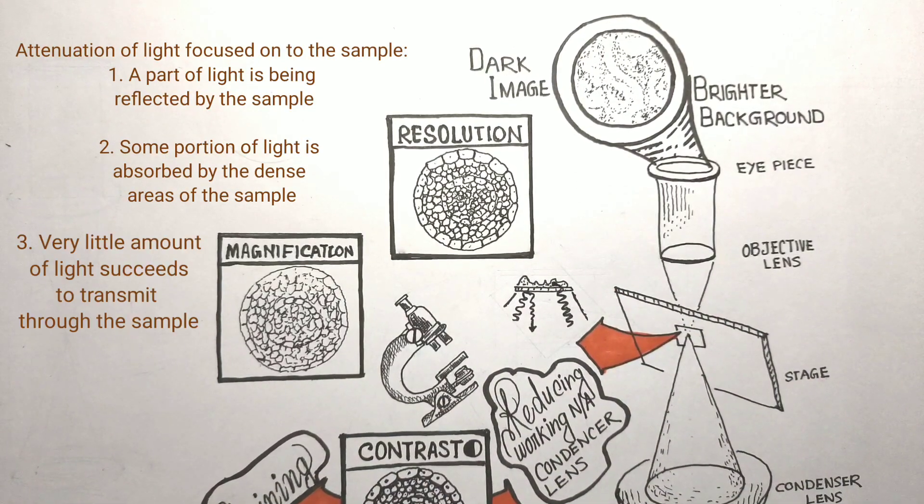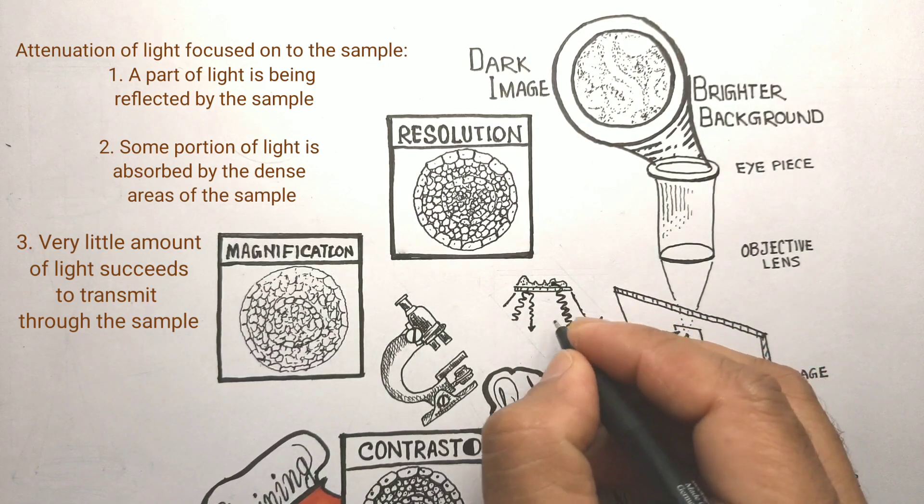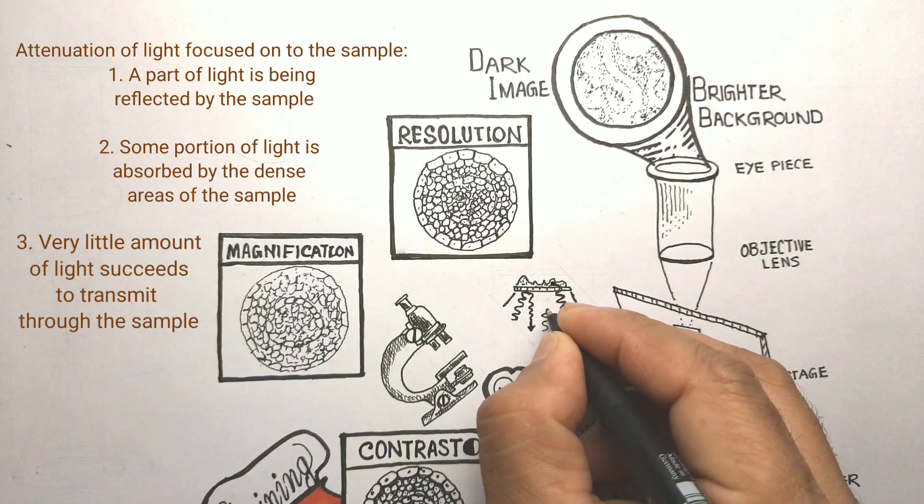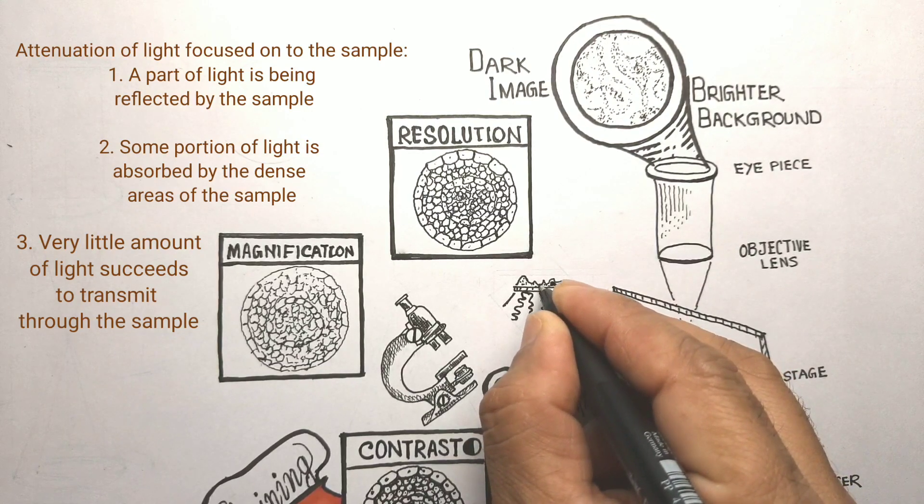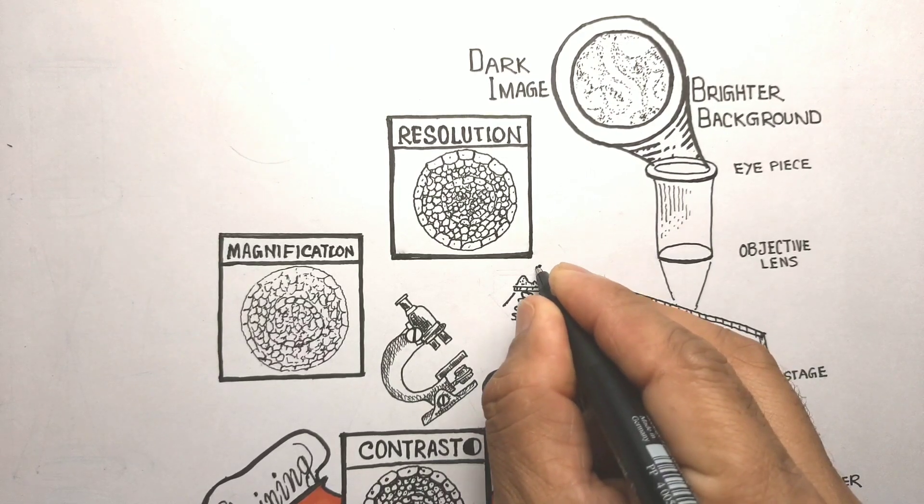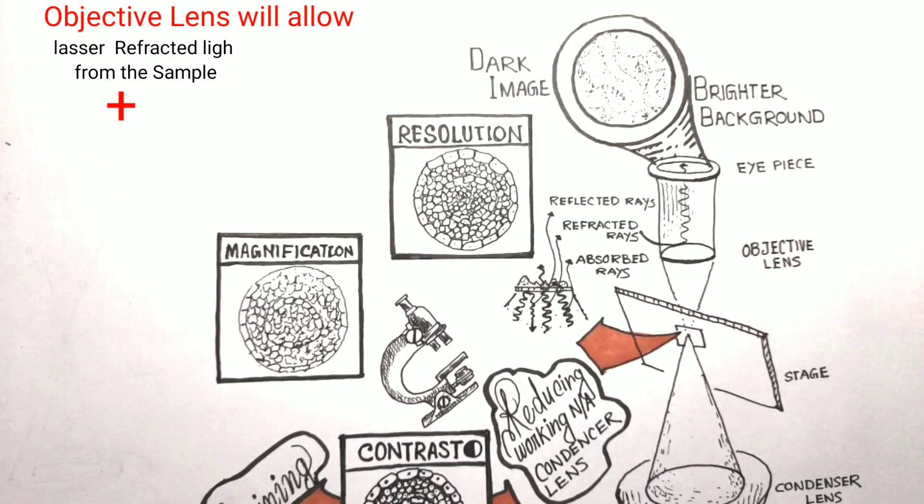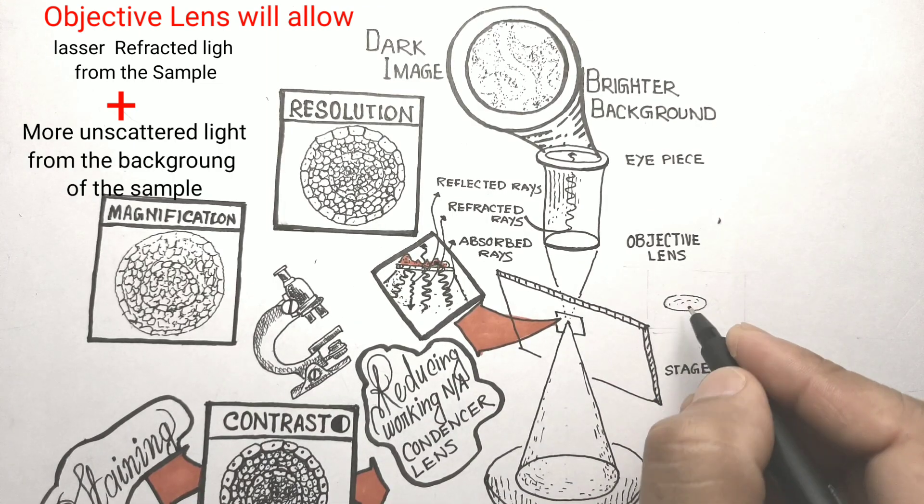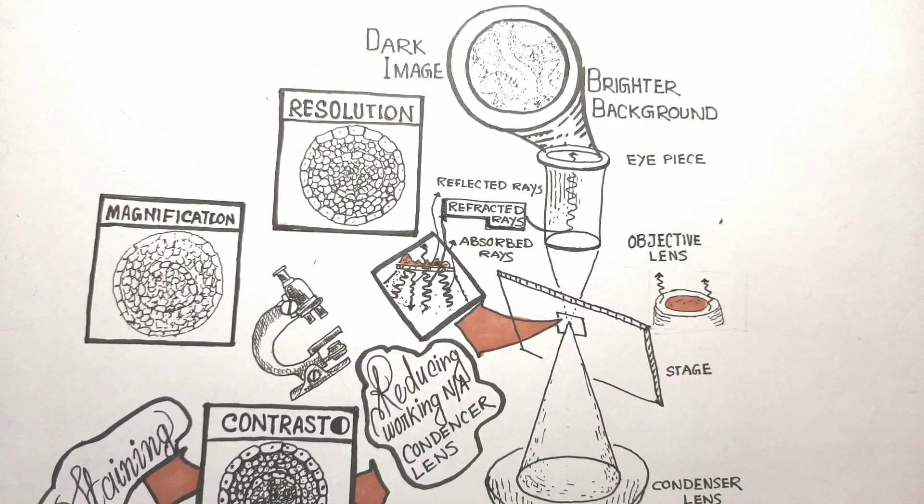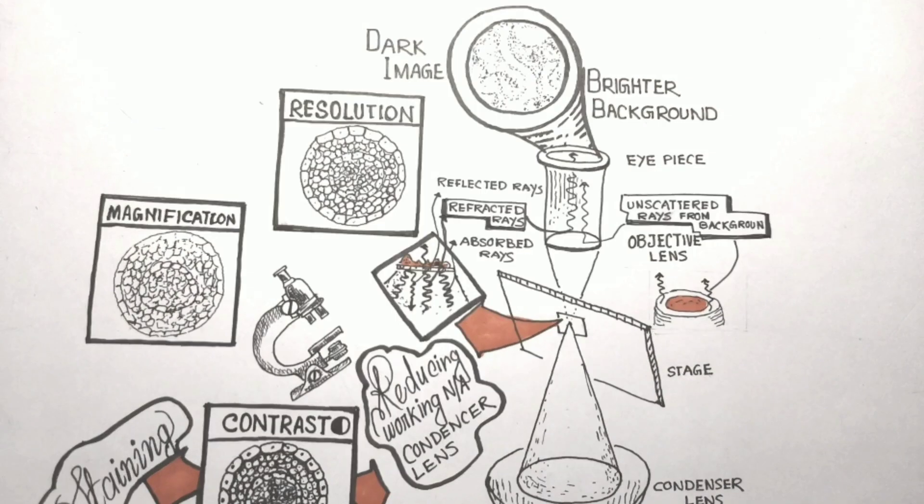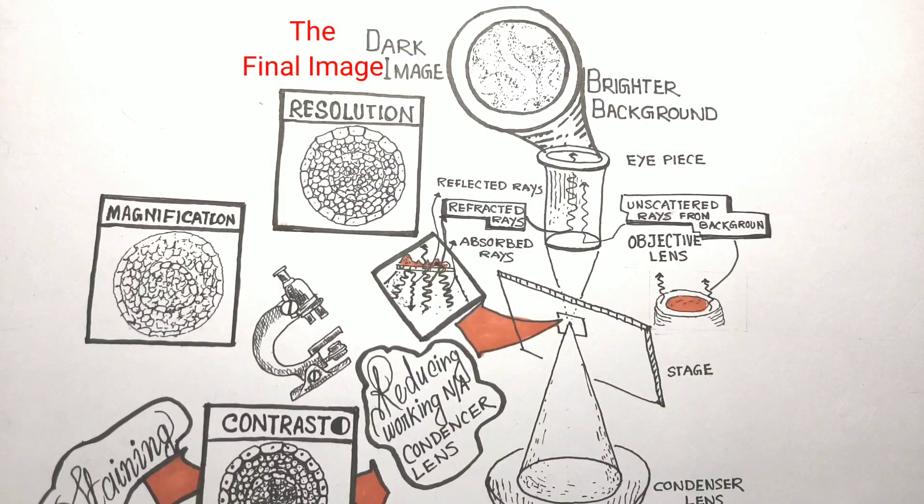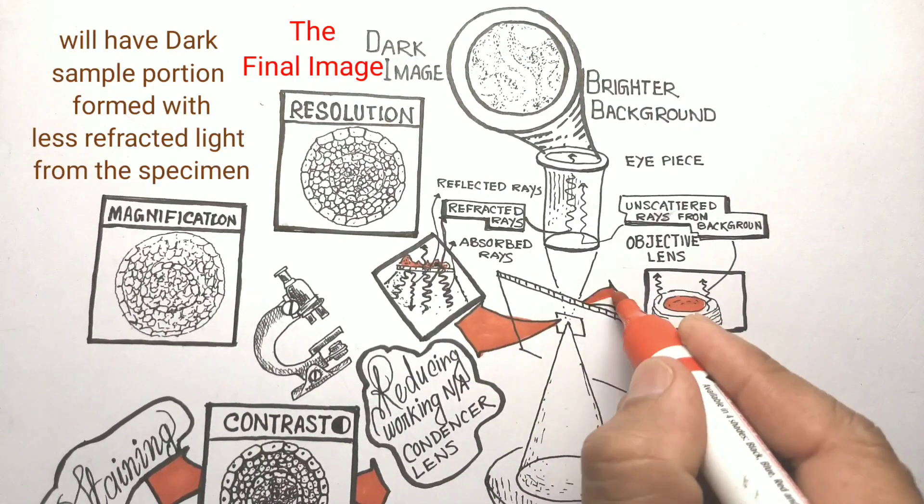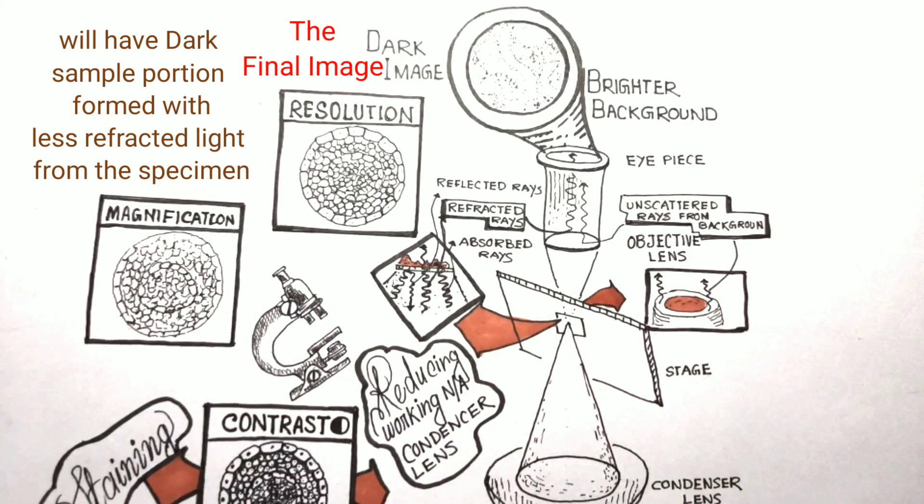Of the light focused onto the sample, some parts are reflected and absorbed, and very little succeeds in transmitting through and is refracted by the sample, which is collected by the objective lens. But along with this lesser amount of refracted light from the sample, a large portion of light from the background is also collected by the objective lens. The background light passes directly without deviation from outside the sample. The final image has a dark sample formed with very little refracted light, and a bright background as comparatively large amounts of undeviated and unscattered light enter the objective lens.